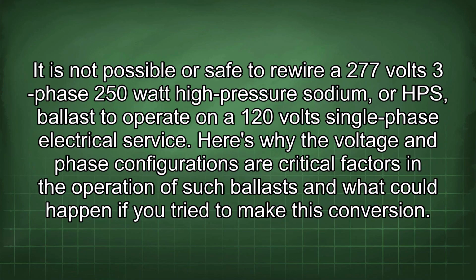It is not possible or safe to rewire a 277 volts 3-phase 250 watt high pressure sodium, or HPS, ballast to operate on a 120 volt single phase electrical service. Here's why the voltage and phase configurations are critical factors in the operation of such ballasts, and what could happen if you tried to make this conversion.